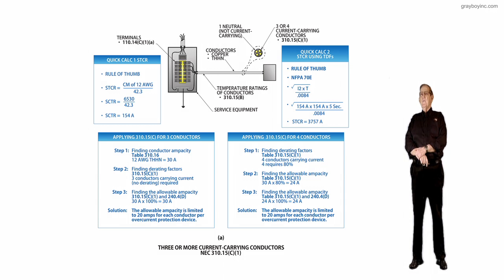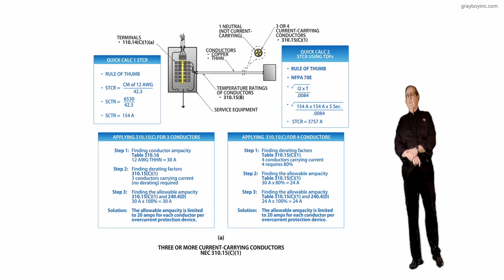Now 3,757 amps, you'd say, how could you have that much current without damaged insulation? Because you clear it in a half cycle, 0.0084 seconds. Over here, it takes 5 seconds to clear it, so you can only put 154 amps on it.